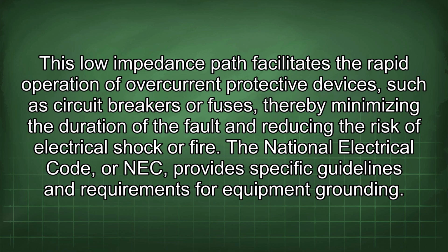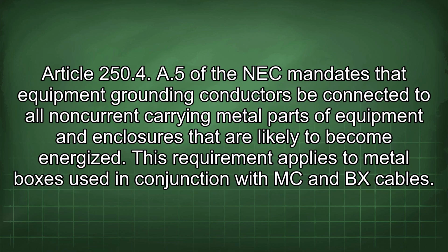The National Electrical Code, or NEC, provides specific guidelines and requirements for equipment grounding. Article 250.4 A5 of the NEC mandates that equipment grounding conductors be connected to all non-current carrying metal parts of equipment and enclosures that are likely to become energized. This requirement applies to metal boxes used in conjunction with MC and BX cables.